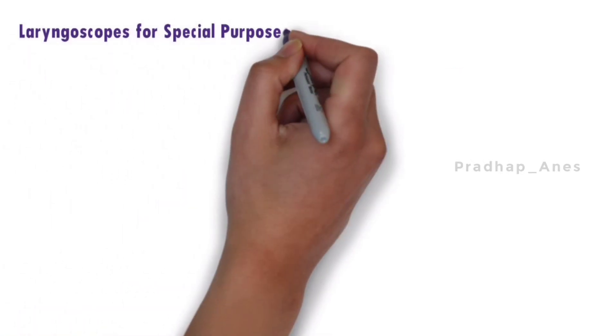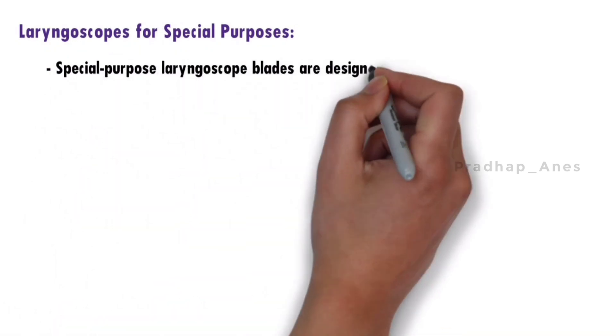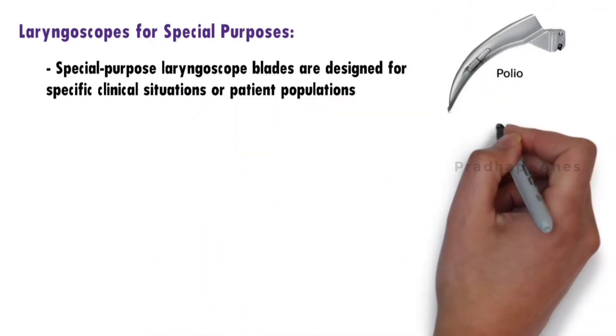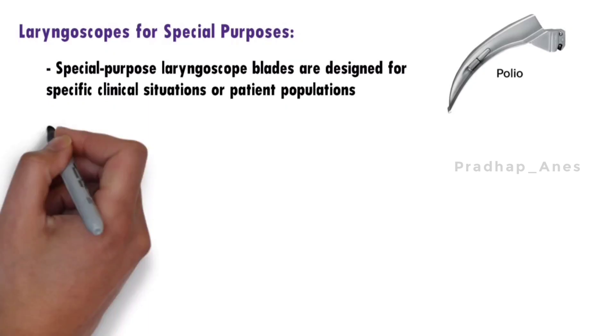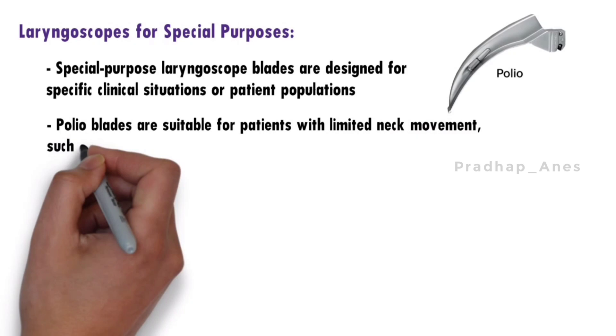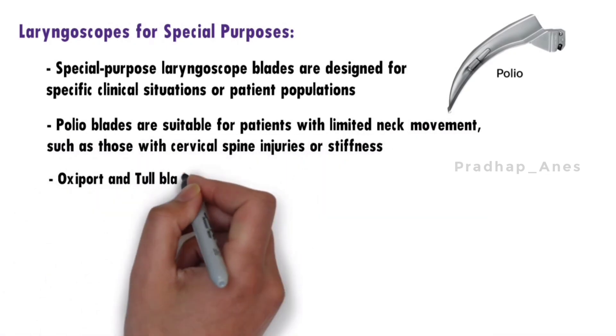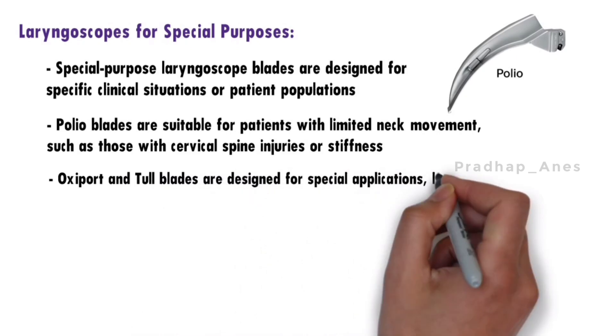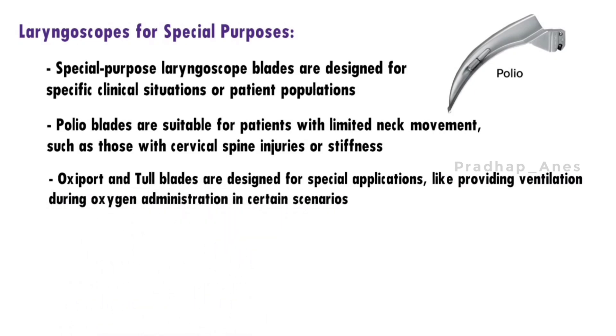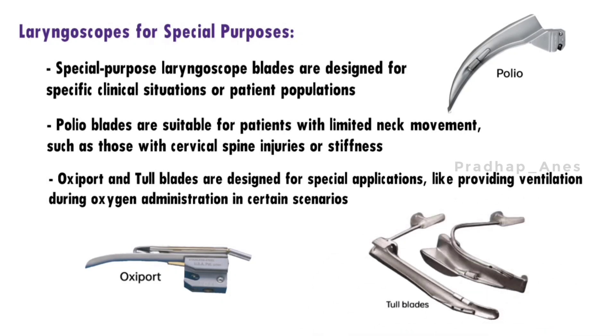Special-purpose laryngoscope blades are designed for specific clinical situations or patient populations. Polio blades are suitable for patients with limited neck movement, such as those with cervical spine injuries or stiffness. Oxiport and Tull blades are designed for special applications like providing ventilation during oxygen administration. These blades are valuable in specific clinical settings but may not be suitable for routine intubations.